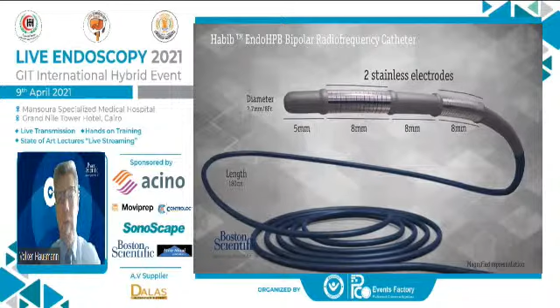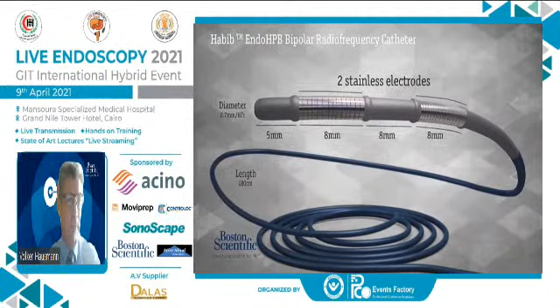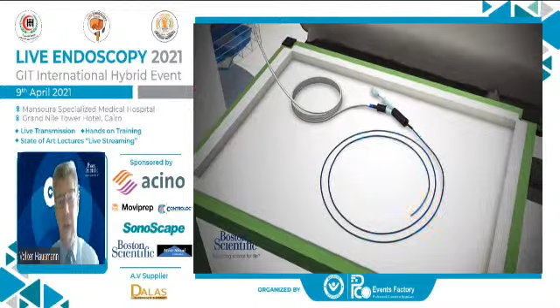But nowadays, it's more than 13,500 procedures done with this probe. We have a lot of peer-reviewed papers, and last year it was rewarded by the Edison Gold Awards for innovative medical technology. I'll give you a quick idea how this catheter works. It's basically two stainless electrodes, 8 millimeters long, 8 millimeters apart, on an 8 French catheter. And this is connected to any kind of electrosurgical generator. You do not need specific dedicated hardware for that.